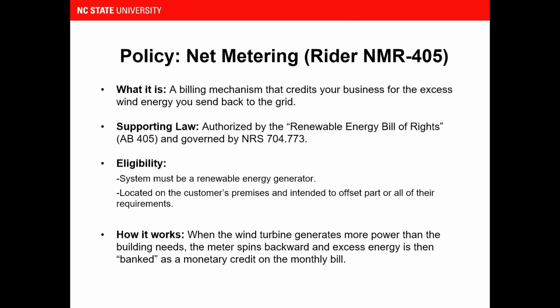As mentioned earlier, the interconnection standards give us the technical permission to connect to the grid, but the financial reason we want to connect is net metering, specifically under Rider NMR-405. This policy, established by Nevada Legislature's Renewable Energy Bill of Rights, is the mechanism that ensures that when our wind turbine produces more power than we're using, like on a windy night when the business is closed, that energy isn't lost. Instead of wasting that electricity, Nevada Energy must take that power and give us a bill credit for it. Essentially, this policy allows the utility grid to function as a giant free battery for your business. You export power when you have too much and draw it back in when the wind stops blowing, ensuring you monetize every single kilowatt hour your turbine produces.